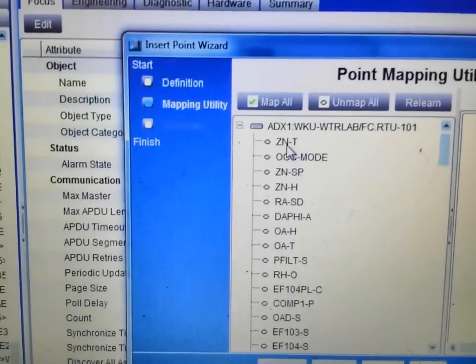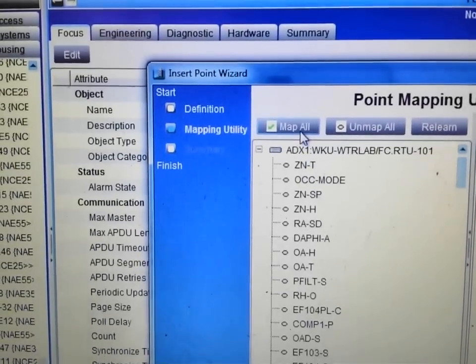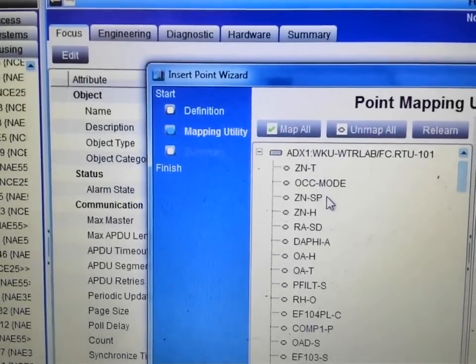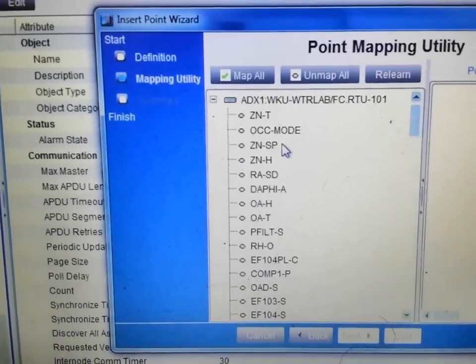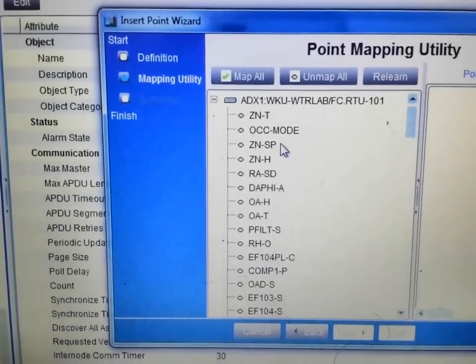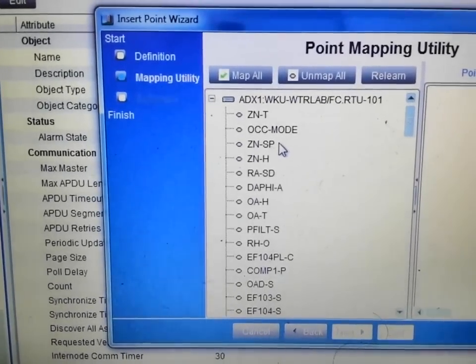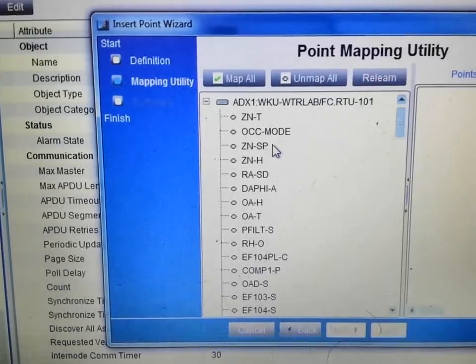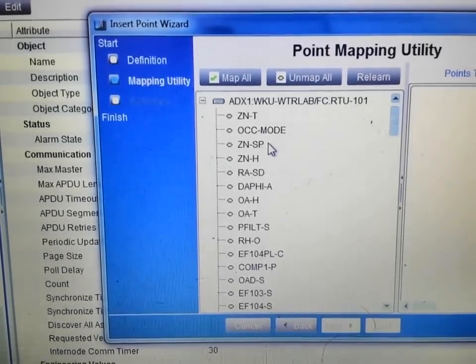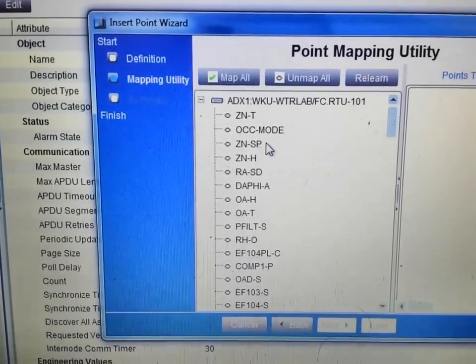I could select the map all feature. I do not recommend doing that. Each of these points does take up some space in your system. I would suggest that you go through and only bring in the ones that are most relevant to your application.